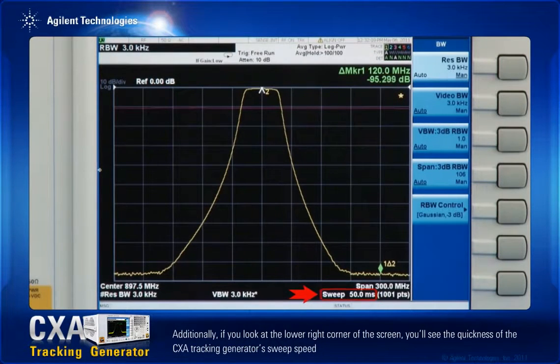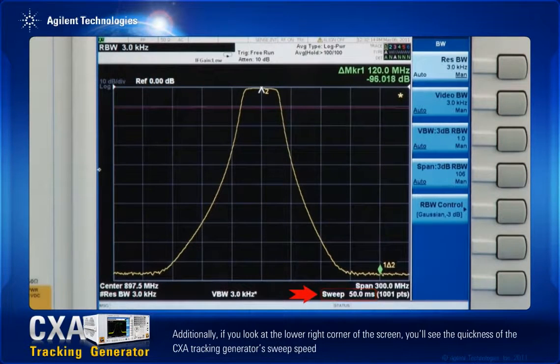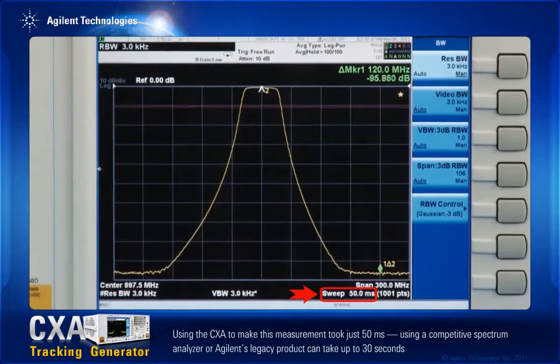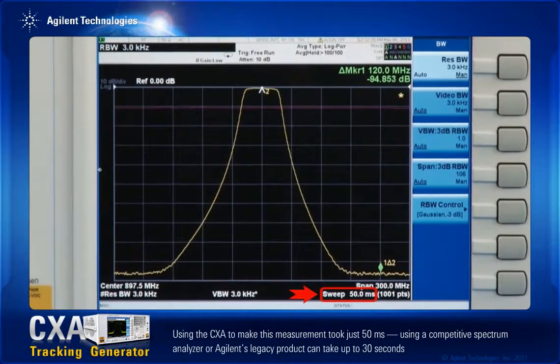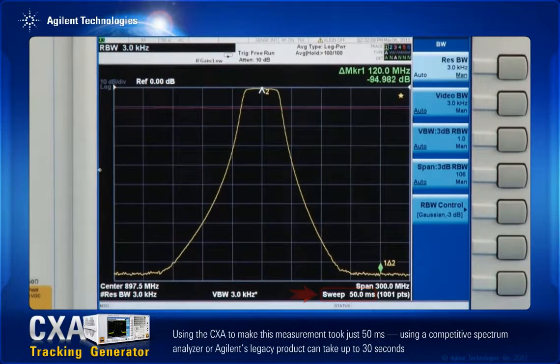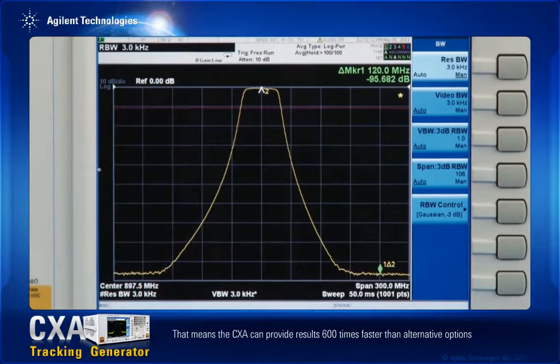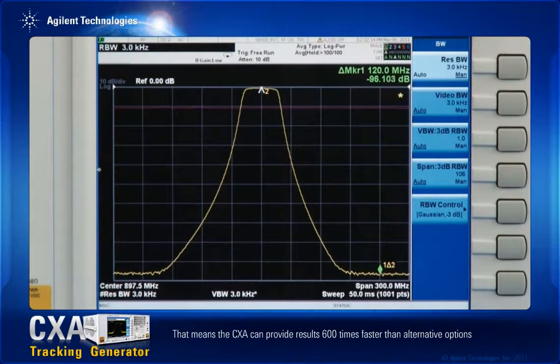If you look at the lower right corner of the screen, you'll see the quickness of the CXA tracking generator's sweep speed. Using the CXA to make this measurement took just 50 milliseconds. Using a competitive spectrum analyzer, or Agilent's legacy product, can take up to 30 seconds. That means the CXA can provide results 600 times faster than alternative options.